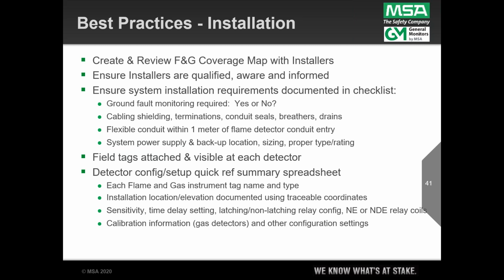I want them to know if this can be a ground fault monitored system or not, because if they don't make terminations properly, that can create ground faults. I don't know if you've ever had to troubleshoot ground faults. It's not fun. Cable shielding, terminations, conduit seals, breathers, and drains: I want to talk about that with them. I want to talk about flex conduit on the flame detectors. I want to talk about the power supply, and making sure it's sized properly. That's more on the design side, but at installation, we're the last line of defense on a properly engineered system. So I want to make sure all that is good.